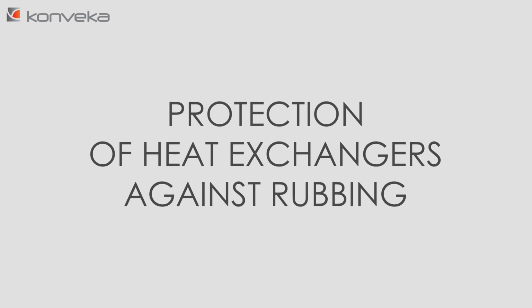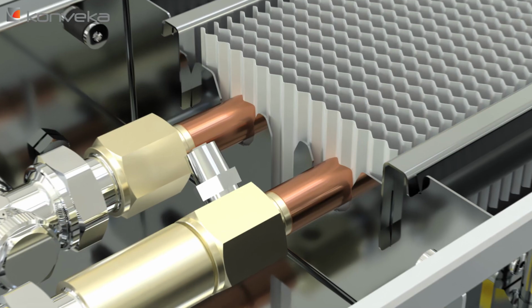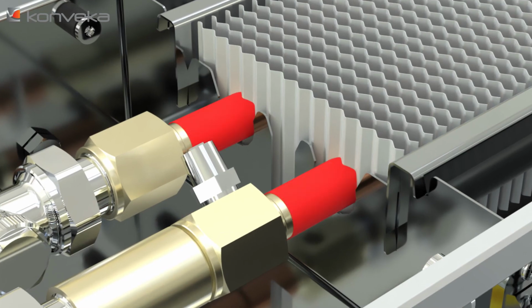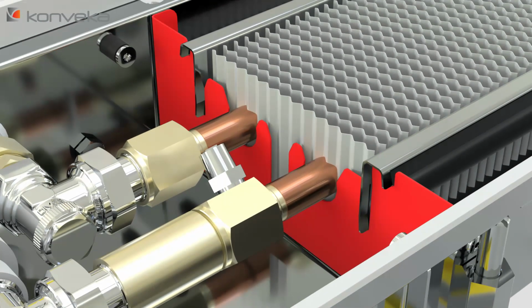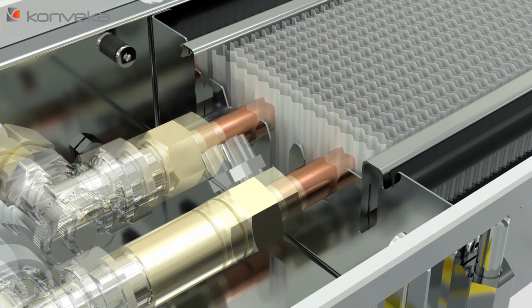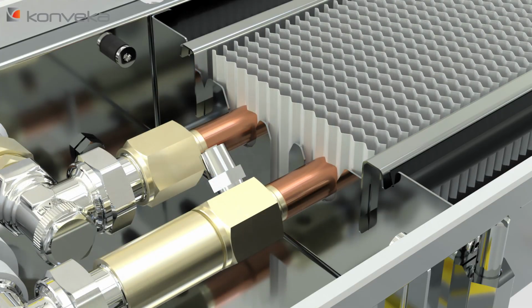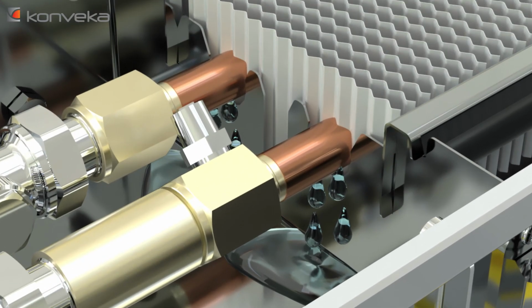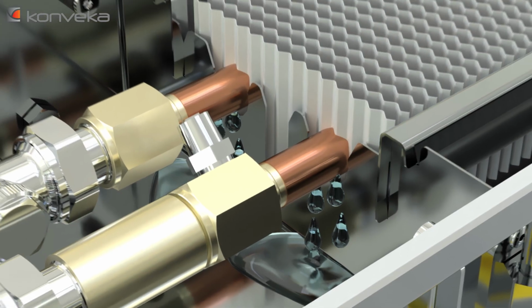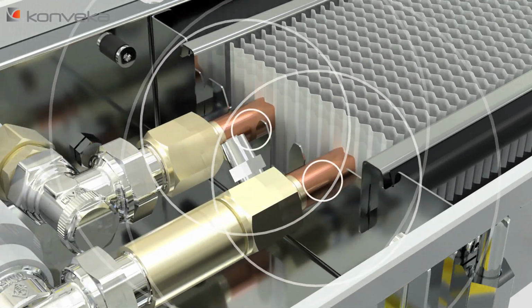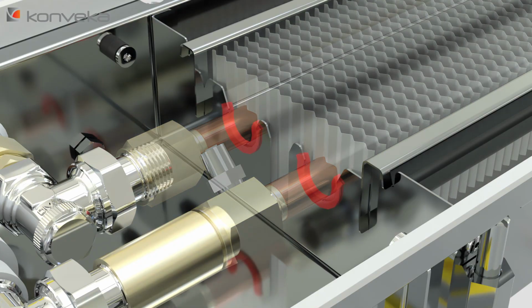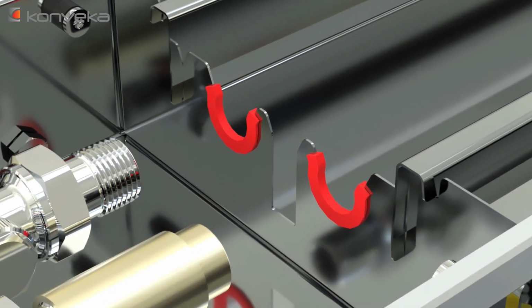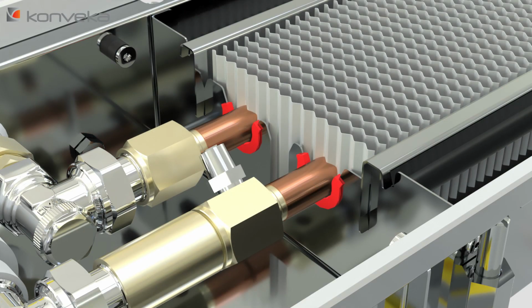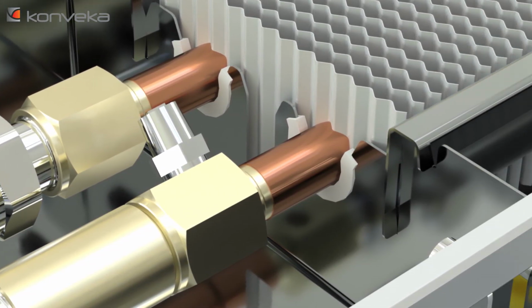Protection of heat exchangers against rubbing. Typically, heat exchangers are attached to the appliance by placing the soft copper tubes into hard steel brackets. At the time of transportation and operation, the heat exchangers move and rub against the brackets, making holes over time and resulting in water leakages. Furthermore, heat exchangers can cause unpleasant sounds when rubbing against the brackets at the time of their operation. To solve these problems, we install special plastic pipe clamps in our convectors that protect the heat exchanger from damage and prevent sounds from occurring. In addition, such pipe clamps serve as brackets, so the heat exchangers are securely mounted in the housing.